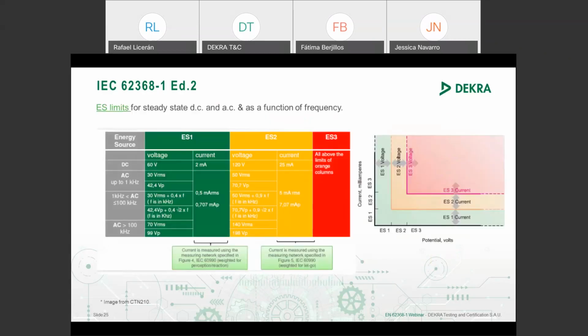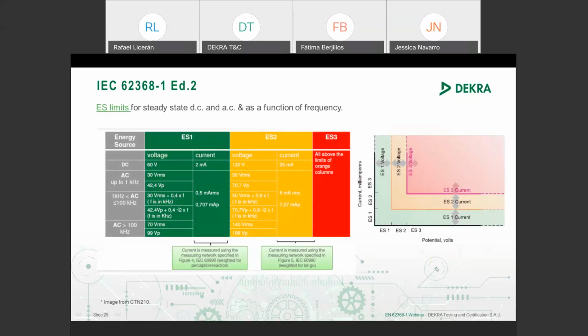In the next table, you can see different voltages and currents used to classify the different circuits. You classify a circuit as ES1 if the voltage is lower than 60 volts or the current is below 2 milliamperes. If my device meets one of them, voltage or current, my connector or circuit that I have analyzed at this moment can be classified as ES1. You can see in the diagram on the right part of the screen that you have to comply with voltage or current in order to give conformity with the classification of the different levels.